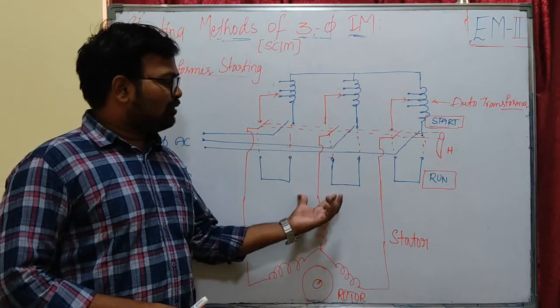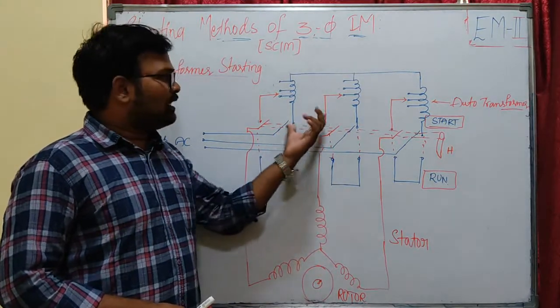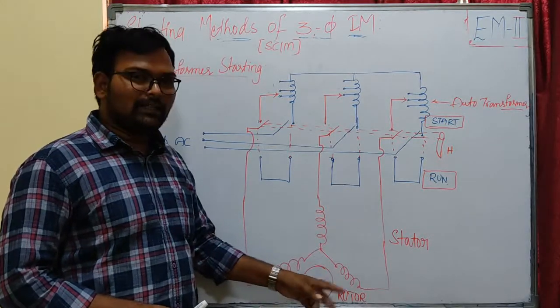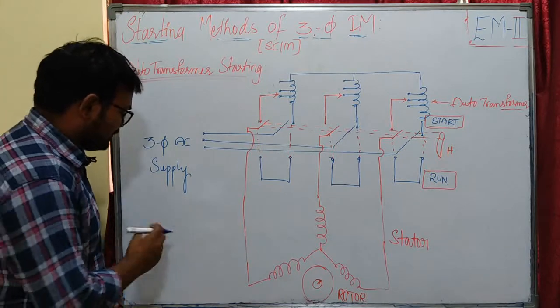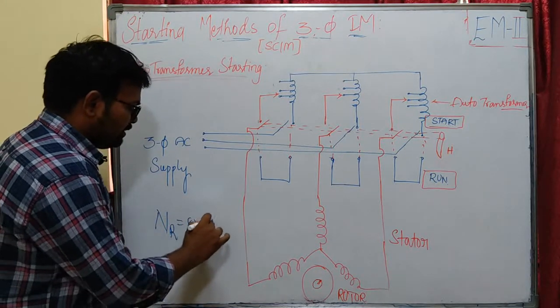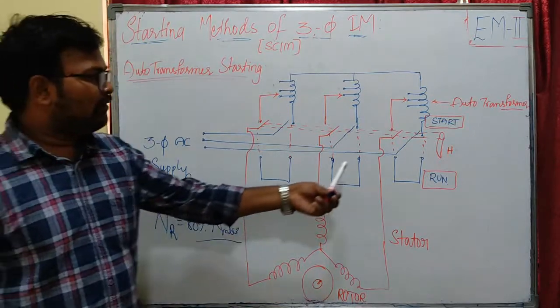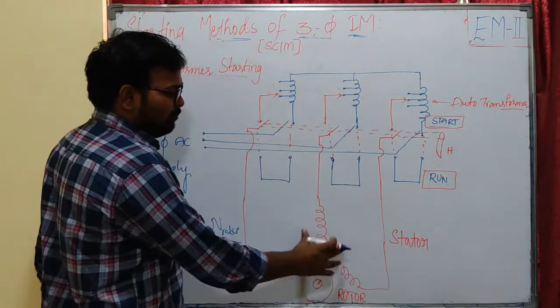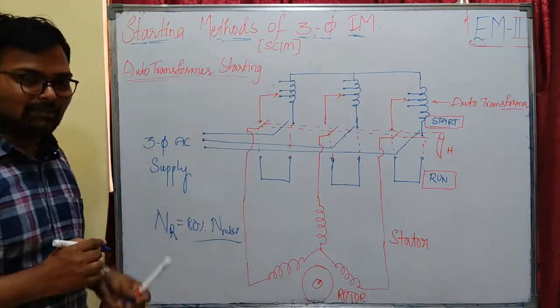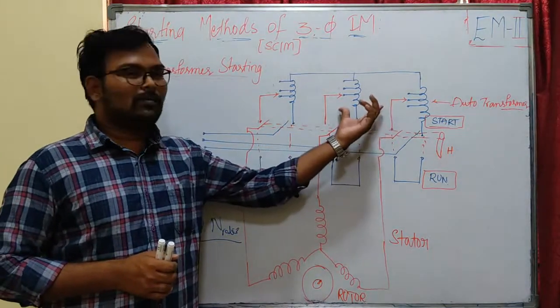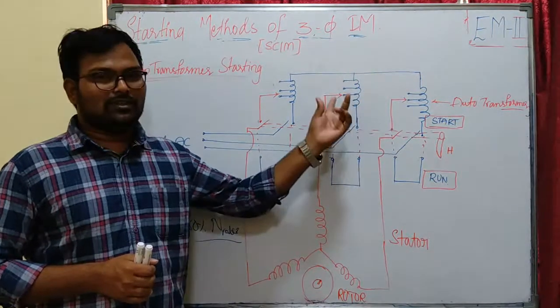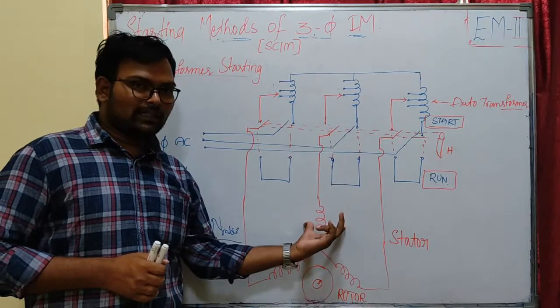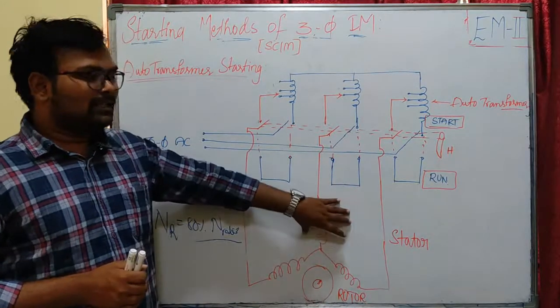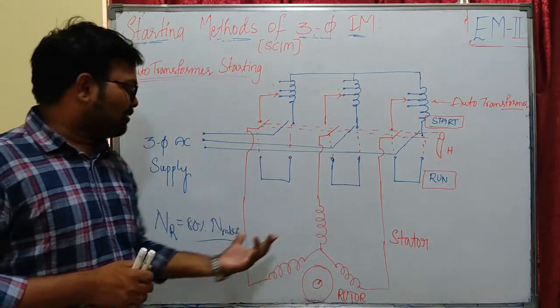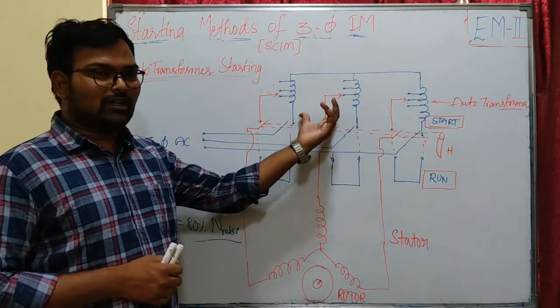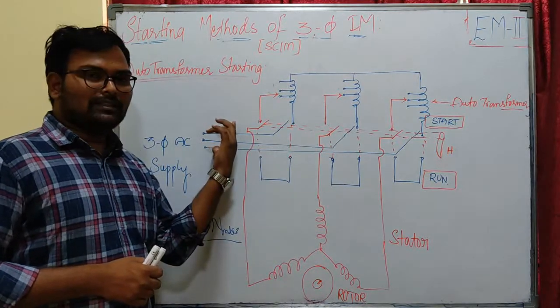Initially the motor stator is supplied with reduced voltage by using auto transformers, and when the rotor attains a speed, let us say around 80% of its rated speed, our auto transformers will be disconnected from the supply and the motor stator will be directly connected to our three phase AC supply. So by using three auto transformers connected in star, we give reduced voltage to our stator circuit so that the starting current of our induction machine will be reduced. After the machine attains 80% of rated speed, we disconnect the auto transformers and connect our stator circuit to the three phase AC supply directly.